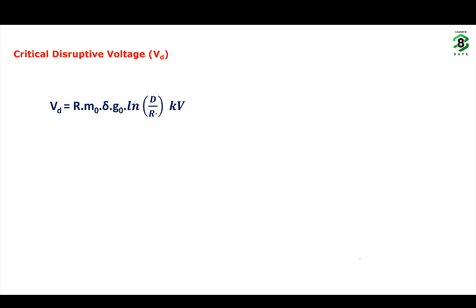So, critical disruptive voltage. The voltage of the conductor at which corona starts to occur is called the critical disruptive voltage. So here you have to remember it is a phase to neutral voltage. It is the phase to neutral voltage, that is, the voltage of the conductor with respect to ground or neutral at which the corona starts to occur is called the critical disruptive voltage. One more thing is, if the conductor voltage, the phase to neutral voltage of the conductor, is less than the critical disruptive voltage, corona will not occur.